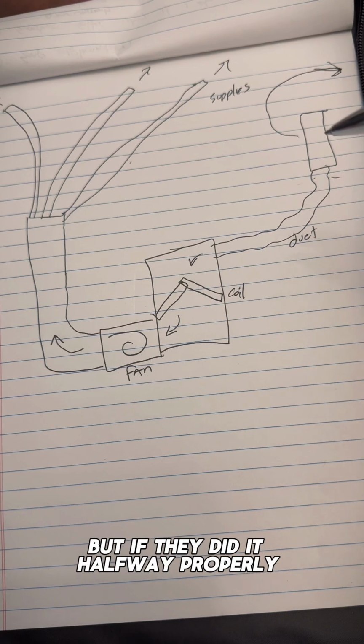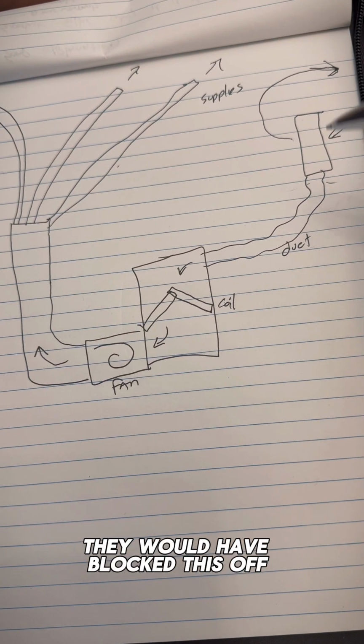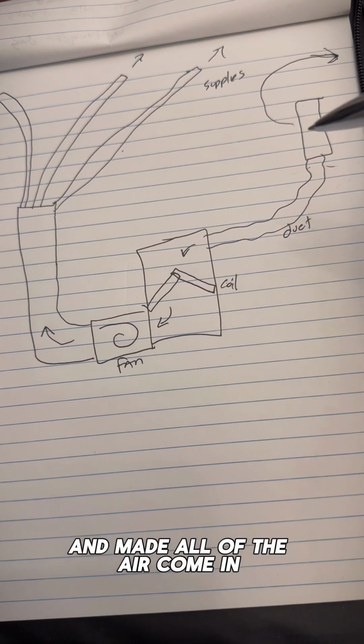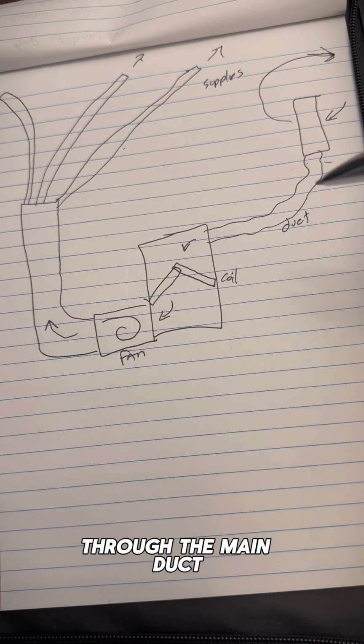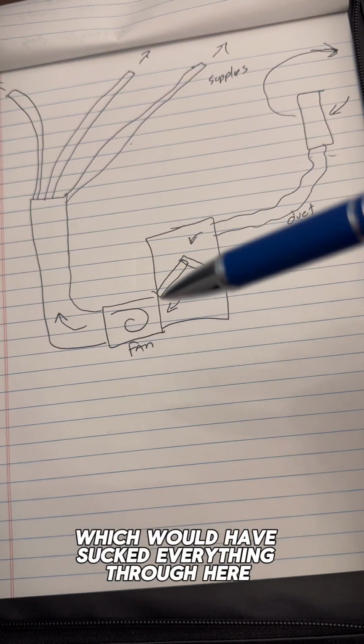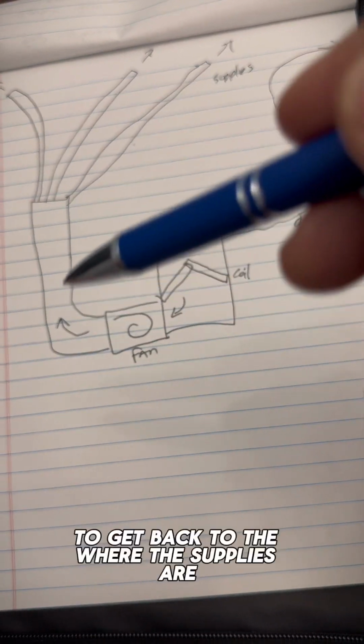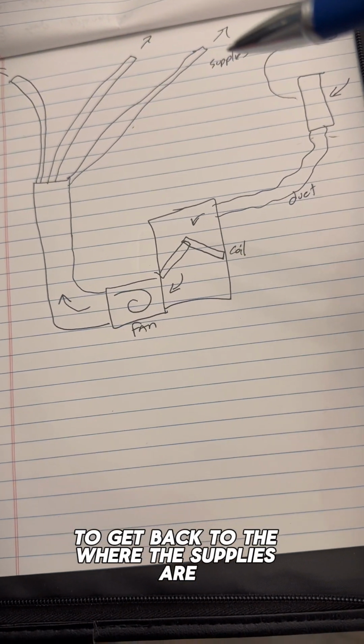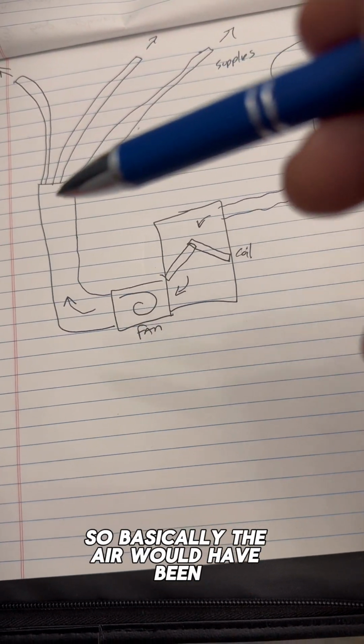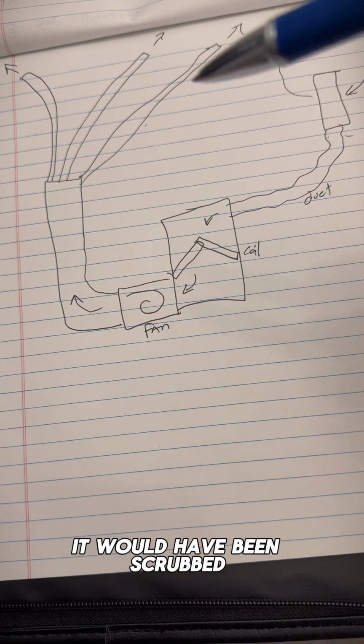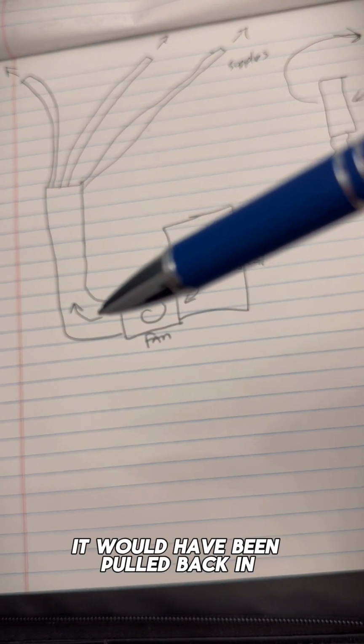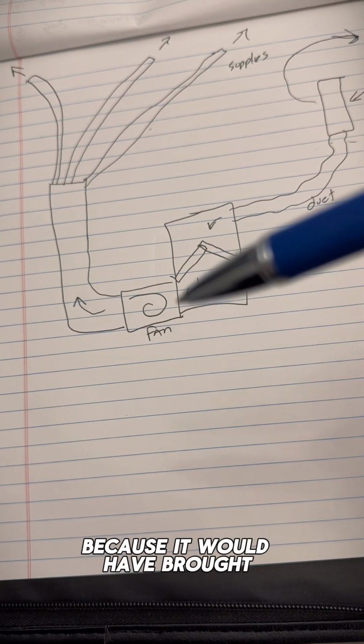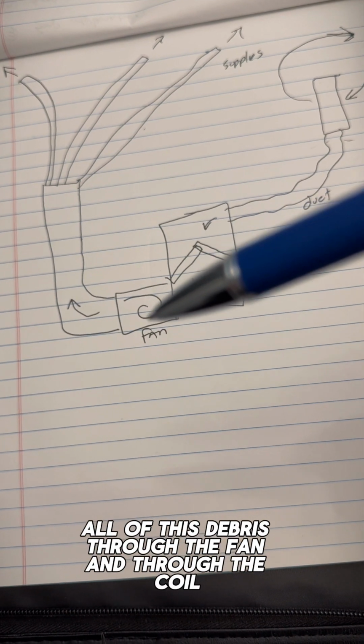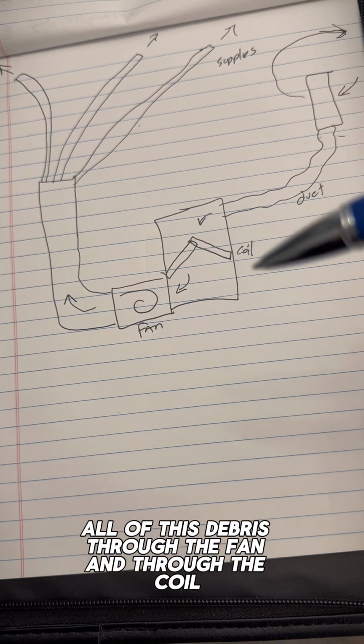But if they did it halfway properly, they would have blocked this off and made all of the air come in through the main duct, which would have sucked everything through here to get back to where the supplies are. So the air would have been scrubbed, pulled back in, and then you see the problem because it would have brought all of this debris through the fan and through the coil.